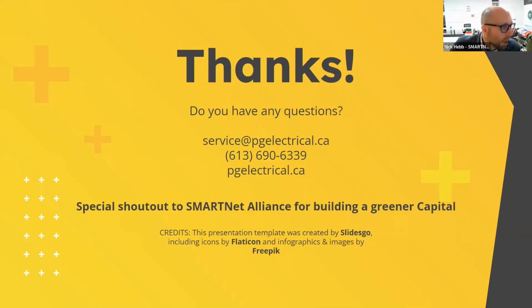Peter has a 200 amp service but his panel is full—can the panel be expanded without increasing the amps? Yes, absolutely. For homes that already have the service size they need but no room in the panel, the solution is a sub panel, commonly called a pony panel. This involves moving some existing loads from the main panel to a secondary device, with overcurrent protection for that sub panel installed in the main panel. This is also common with smaller 100 amp panels when you just need extra room for a new system.